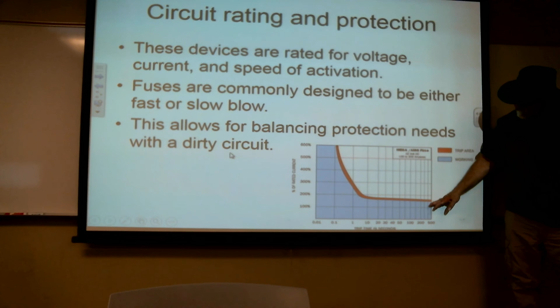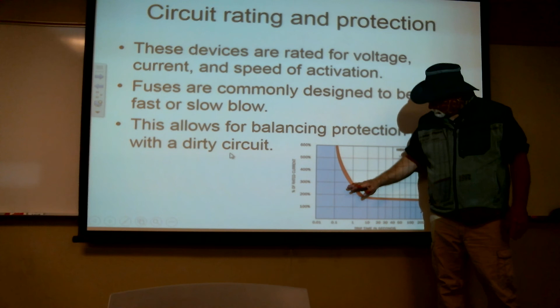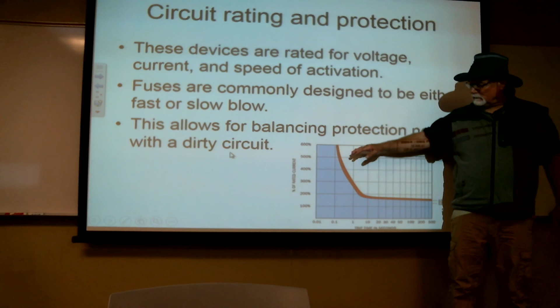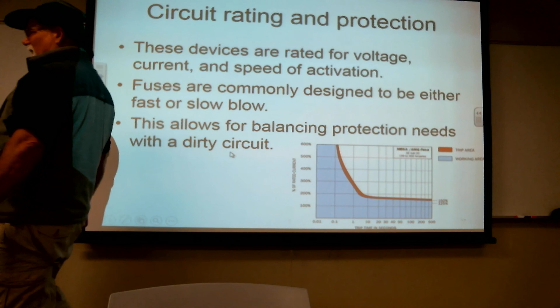So this chart sort of shows trip area versus working area. At a low, 100% of its current rating, you've got 500 seconds or maybe even more and it's not going to trip. But if I get up to about 300% of its current rating, it's going to trip in 1 second. And if I start getting higher, 6, 7 times, it's going to trip quite a bit quicker. That's actually a fairly not-slow response circuit breaker; most of them are actually quite a bit quicker than that. What you'd actually see is this being 500 milliseconds or half a second would be a more accurate description.